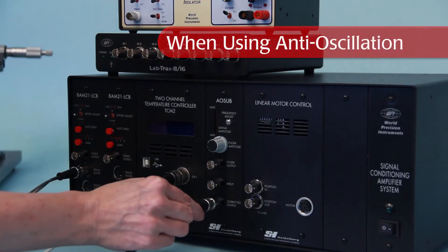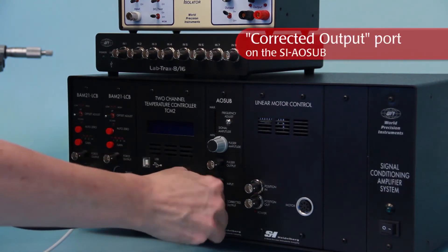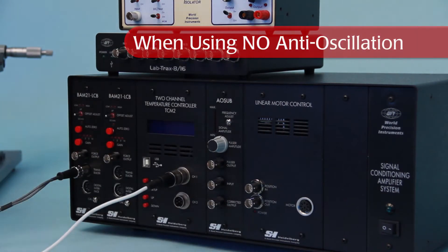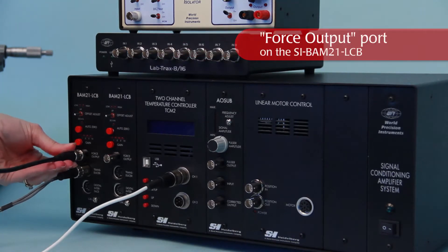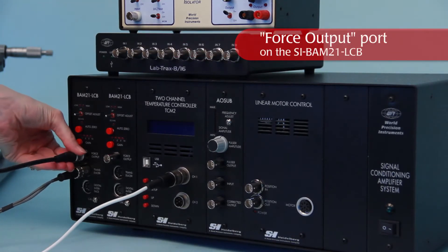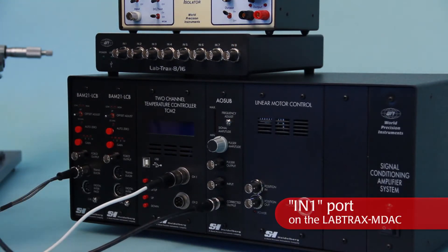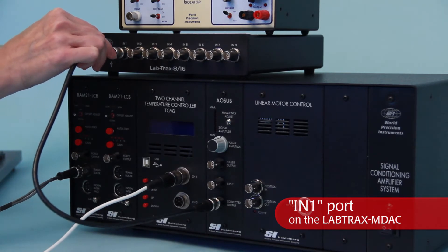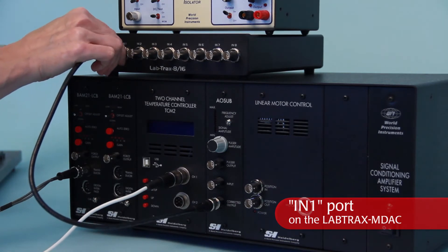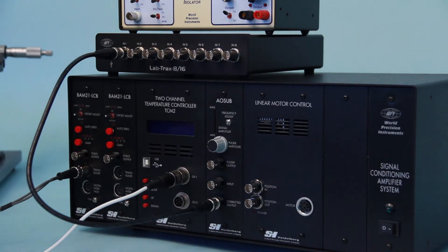If an anti-oscillation module is used, connect a BNC cable to the socket labeled corrected output. If an anti-oscillation module is not used, connect a BNC cable to the socket labeled force output on the front of the BAM21 amplifier. Connect the other end of this cable to the analog input on the data recording device designated as the force recording channel, like the IN1 connector on the Labtrax MDAC.